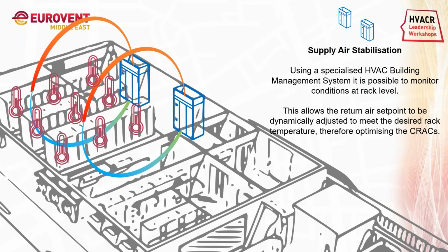One of the possible cases is supply air stabilization in a DX system. As I told you, the DX systems are running on a return air basis, but with an efficient building management system, it is possible to monitor conditions at rack level. So we can have additional sensors at the racks and monitor the temperatures at rack level. This will allow the return air set point in the CRAC unit to be dynamically adjusted so that the rack temperatures reach a desired temperature.